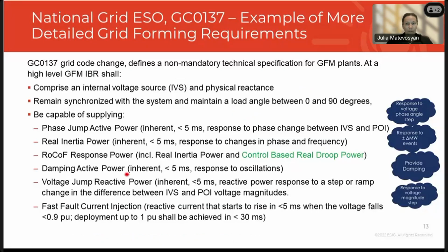Right, as we move to National Grid's requirements, you'll see that those are relatively similar to AEMO's requirements. So again, provide phase jump power, real inertia power. So that's kind of to the point of limiting rate of change of frequency after an event. RoCoF response power. So this is where they combine what they call real inertia power with control-based real droop power. And I have this in green because also grid following inverters can provide this control-based droop power. So that's your fast frequency response or maybe primary frequency response. So these two responses combined are supposed to limit rate of change of frequency.